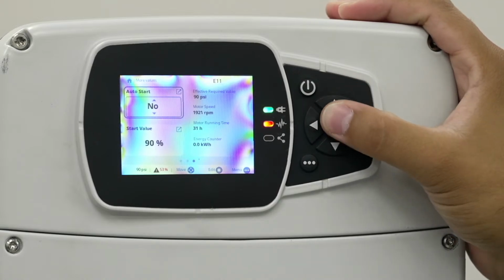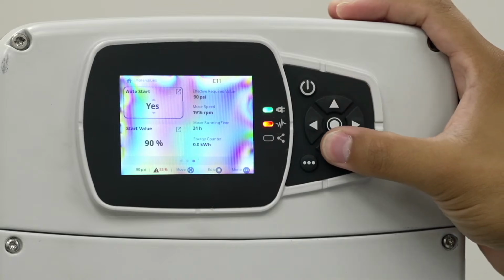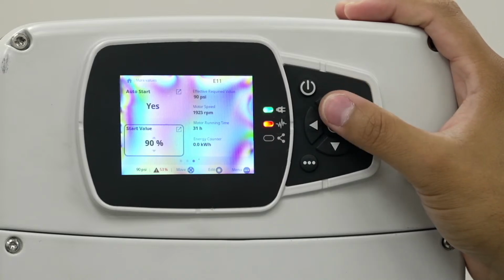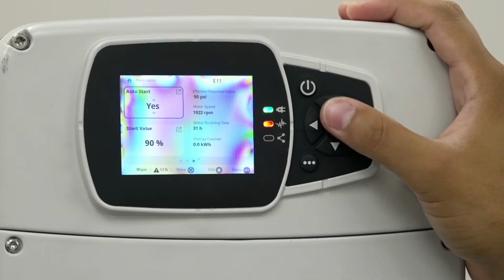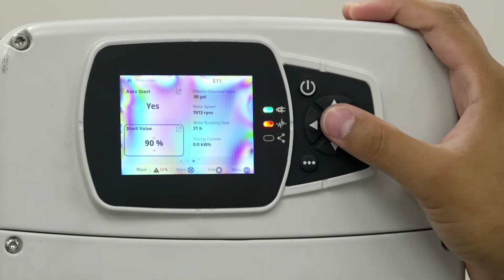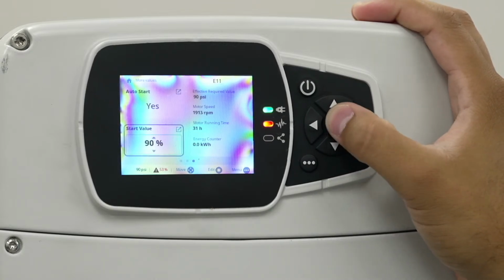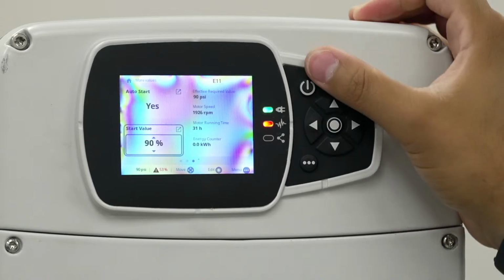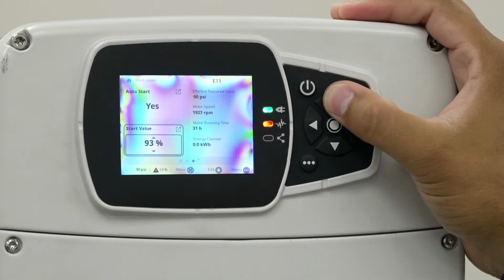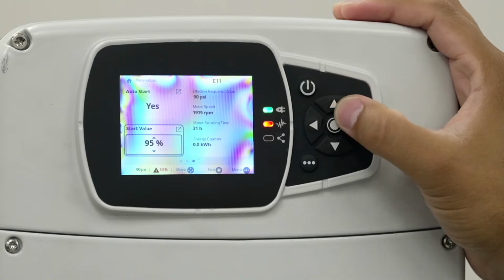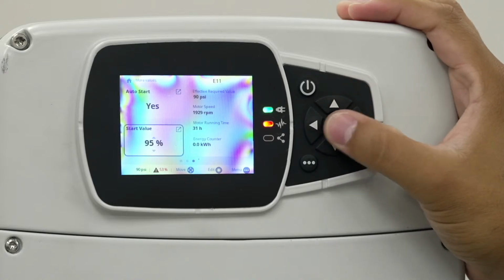It's just if you want that system to automatically start itself or not. It's kind of like manual mode or not. We're going to put it in auto so it responds by itself. And then that start value. Once again, if you were seeing too much of a pressure drop and you wanted to tighten that window, we can increase this to 95% now.